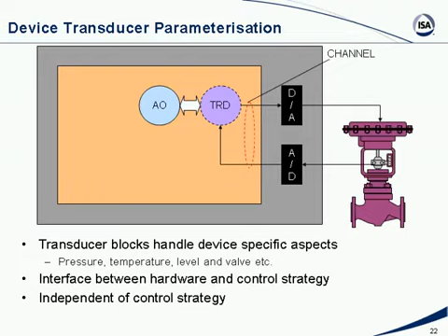Okay. So this is where you can perform all the calibration as well. Most of the diagnostics is found here. You do valve performance analysis. You get operational statistics on how many times the valve has opened and closed and how far it has traveled, etc. All of this is inside the transducer block, okay? And you use the same configuration tool to configure the devices, to configure the fieldbus, and to build a control strategy. All of this is done from the same tool. So it becomes quite easy, compared to the past where you configured the control system using one software and then had to use a handheld to configure the device. That's no more. All can now be done in the same single tool.